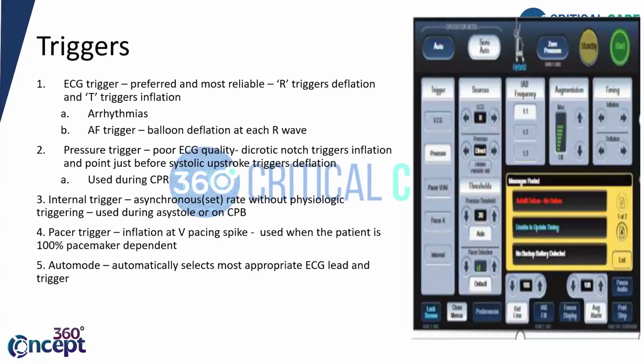arrhythmias or when you have AF, when the rate is very, very high. So the AF trigger can be used. So balloon deflation happens at each R wave. So the R wave is not disturbed in AF, correct? So that is why it is easy when a patient has AF on the monitor. So you can change from the pressure trigger. You can put it on ECG trigger. So it'll identify the R wave and it will time the inflation and deflation of the balloon. Okay.